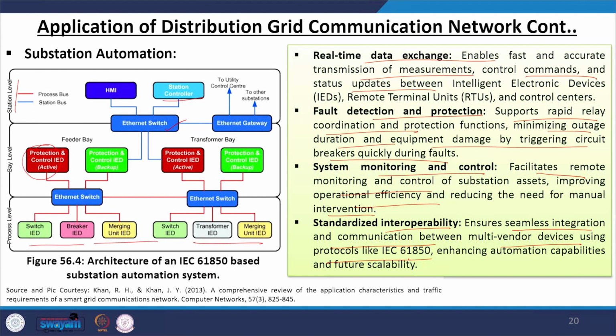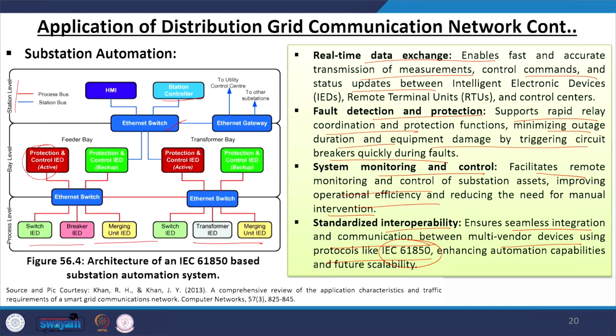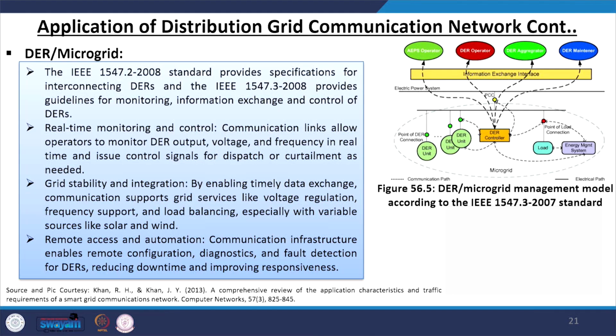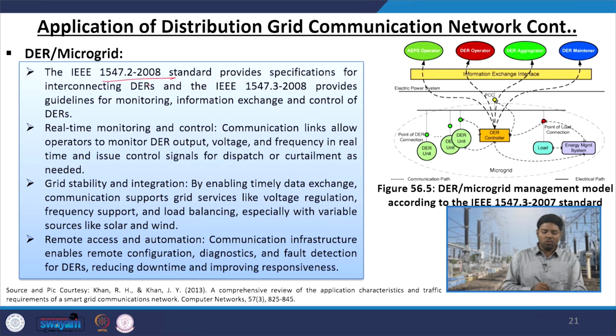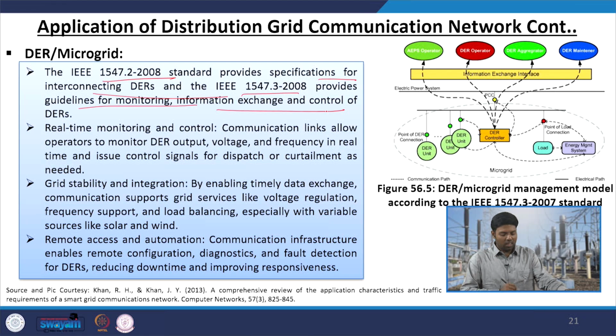So, in the substation there is not only one make, right, multiple devices are made by multiple vendors, multiple manufacturers. So, that has to be synchronized with a proper protocol. So, that is done by the IEC 61850 standard. Then microgrid and DER control. You have the IEEE 1547.2 2008 standard, which provides specifications for interconnecting DERs, and the 1547.3 2008 provides the guidelines for monitoring, information exchange and the control of DERs.